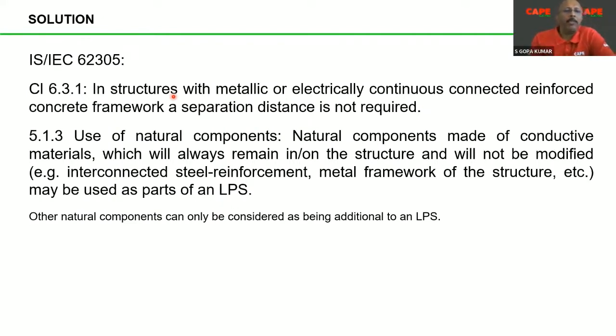Predominantly in India, for large buildings, we always use RCC or PEB. So this clause says that in structures with metallic or electrically continuous connected reinforced concrete framework, separation distance is not required. That means in RCC buildings, separation distance is not necessary if you make use of it. In PEB buildings, separation distance is not necessary if you make use of it.